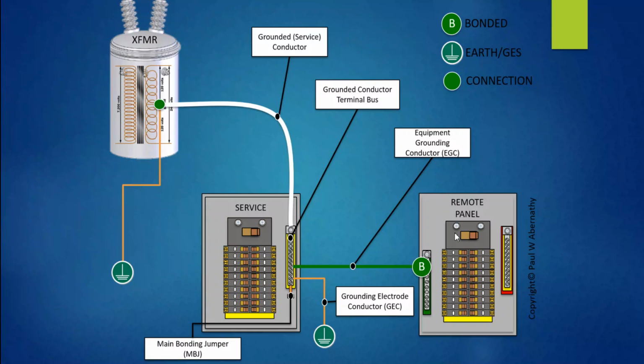It is sometimes referred to as a sub panel, but I've never seen it installed in a sub, nor have I been in a sub where I've seen a panel like this. Really, sub is a derivative of the fact that it's a subset of the service equipment, or a downstream electrical panel. So we call it a remote distribution panel or remote panel, however you want to call it. You'll notice on this end, you have two different bus bars. Here's the grounded conductor bus bar, which is isolated. I show this by the yellow with the red around it. And over here, the green means this one is actually connected to the enclosure. It has an equipment grounding conductor downstream. As we all know, you're required to have 4 conductors feeding remote distribution panels in order to have a separate grounded conductor, in our case a neutral, and a separate equipment grounding conductor bus.